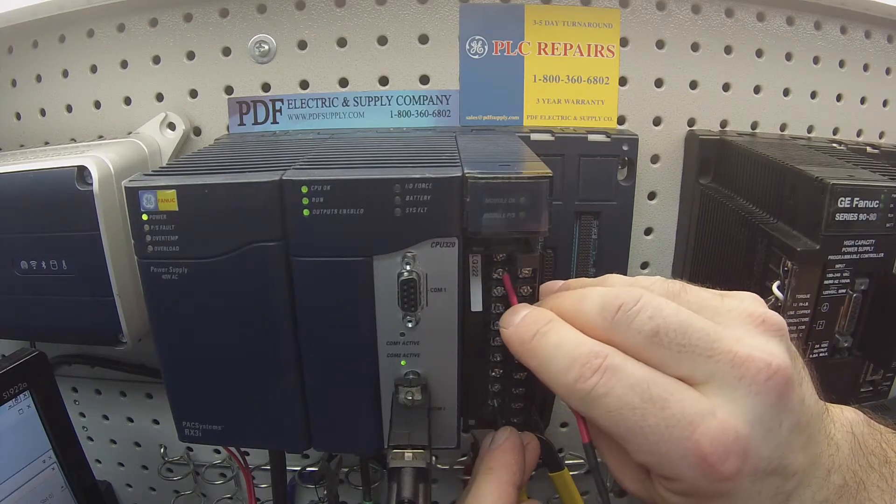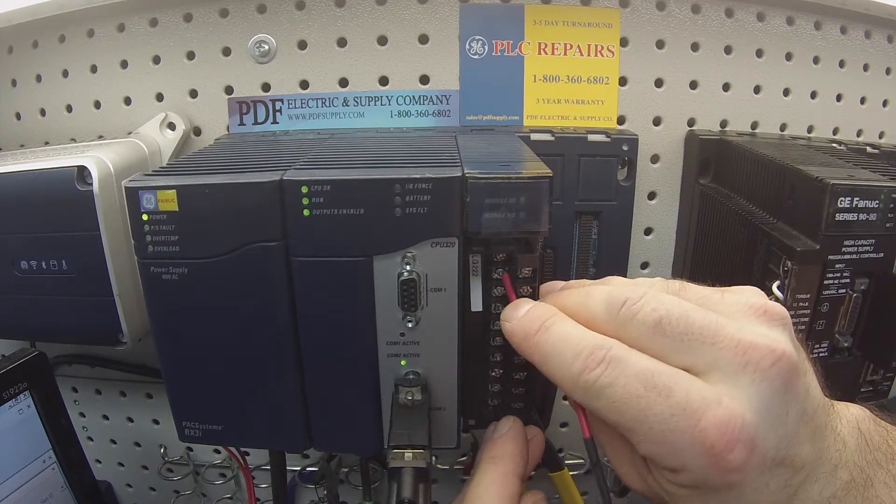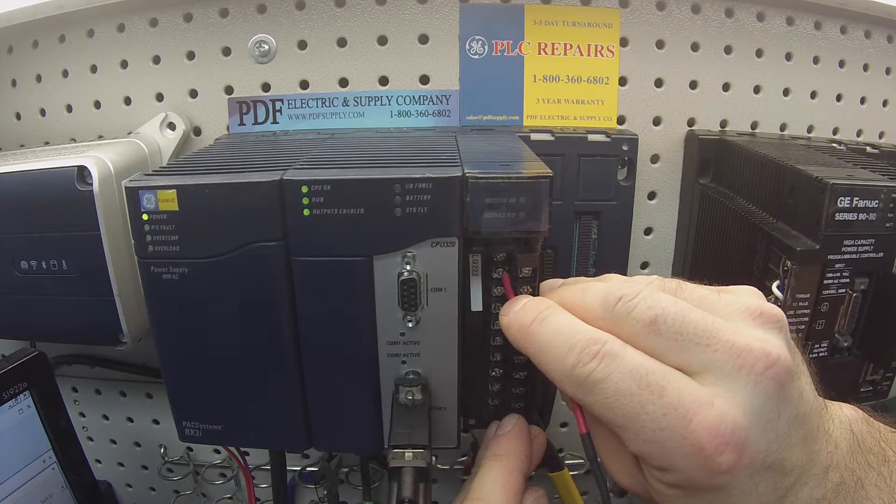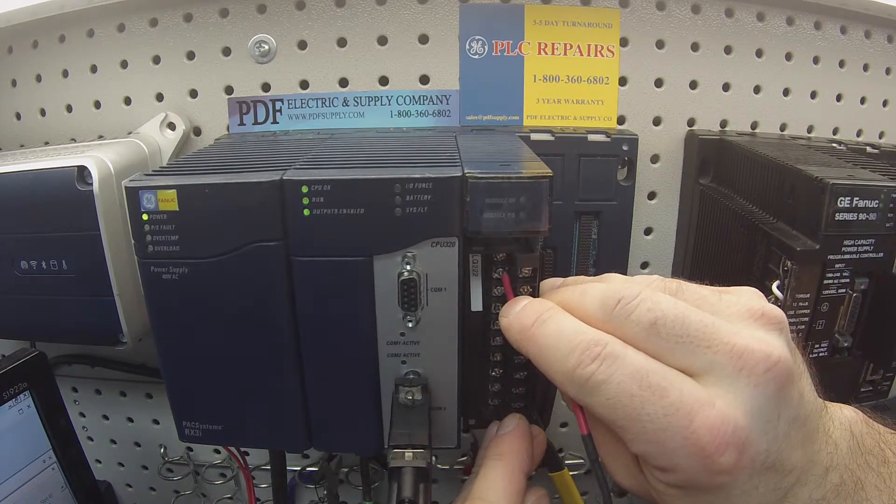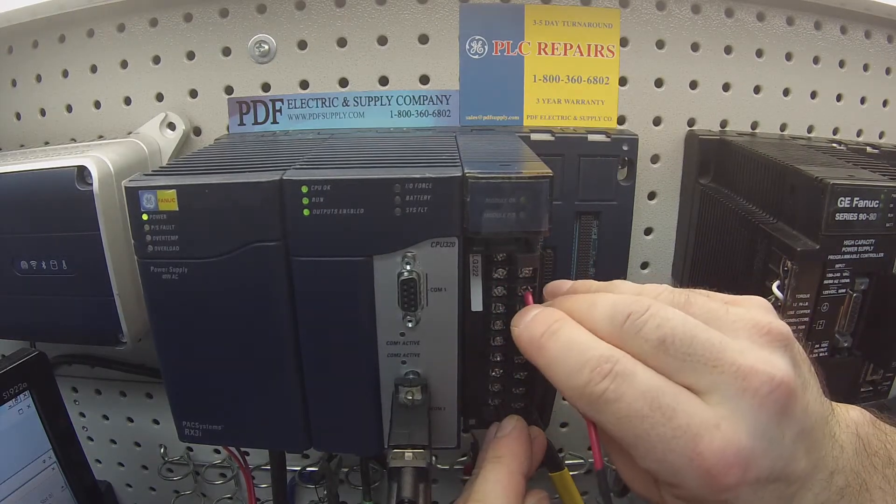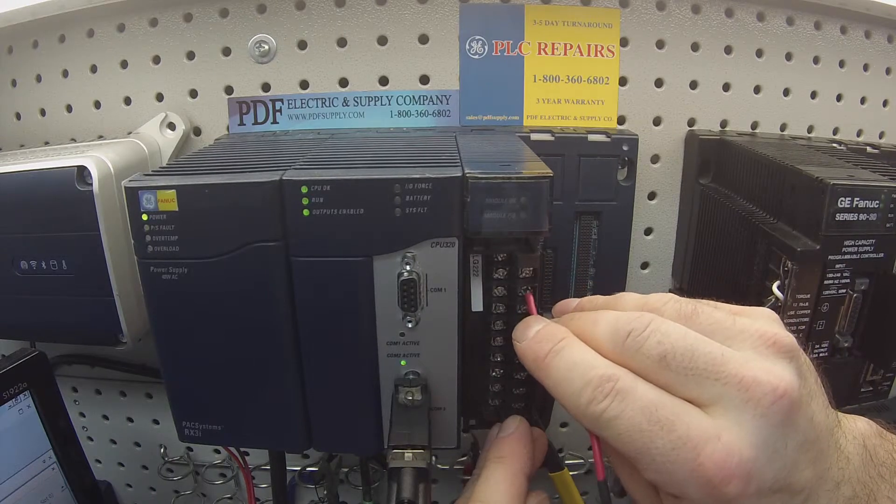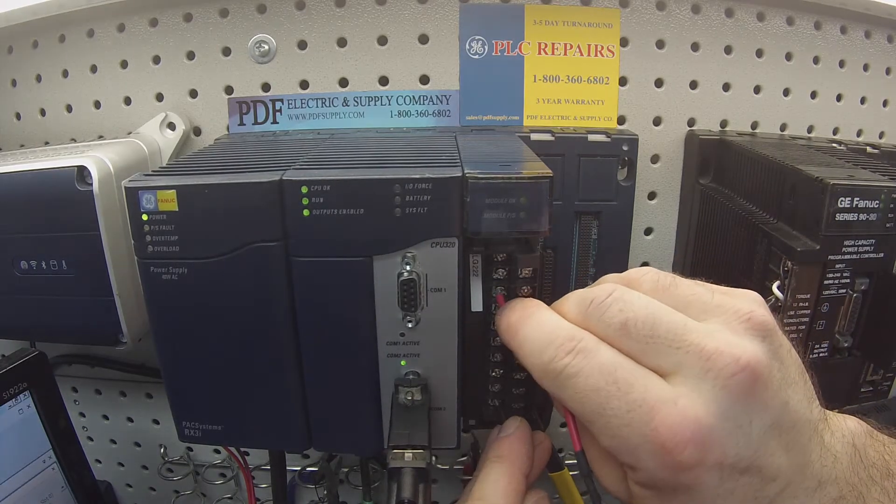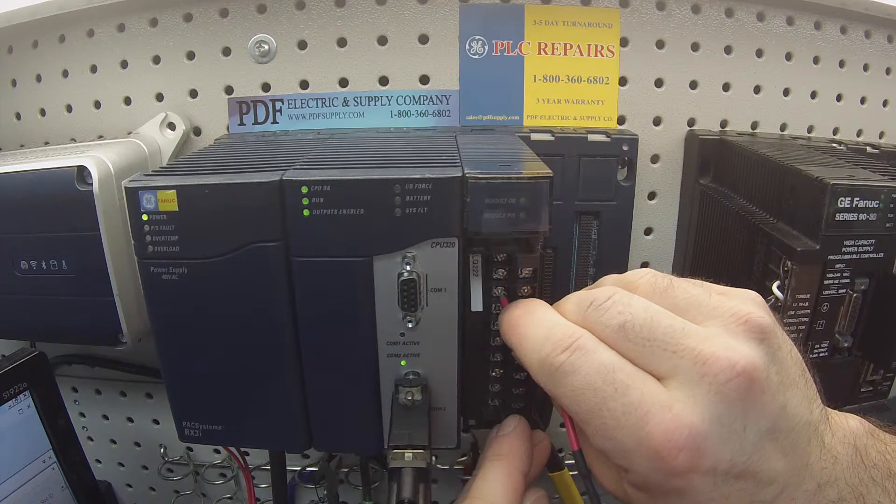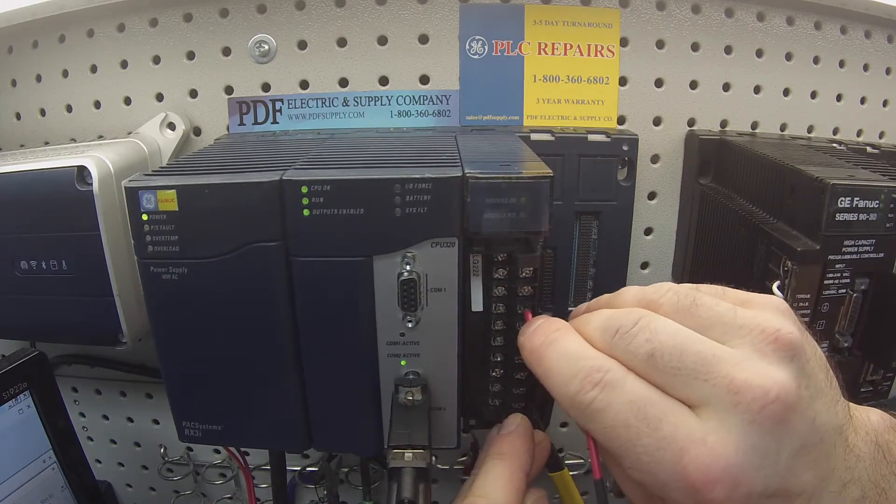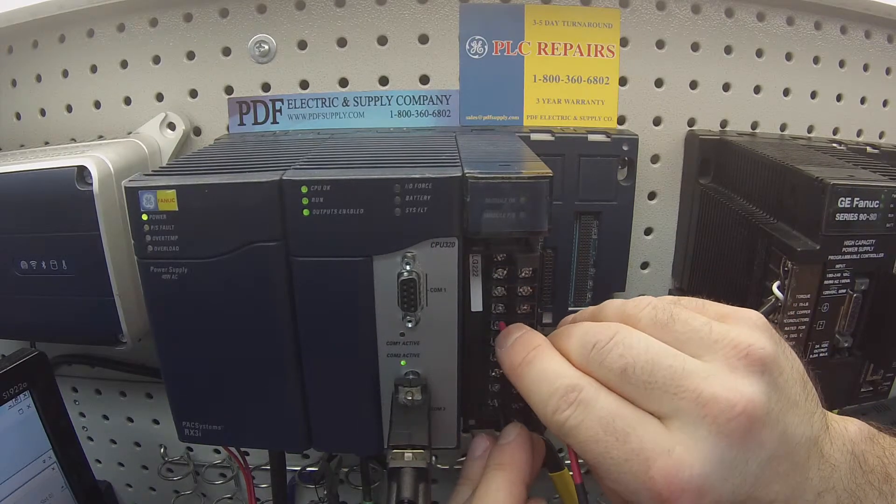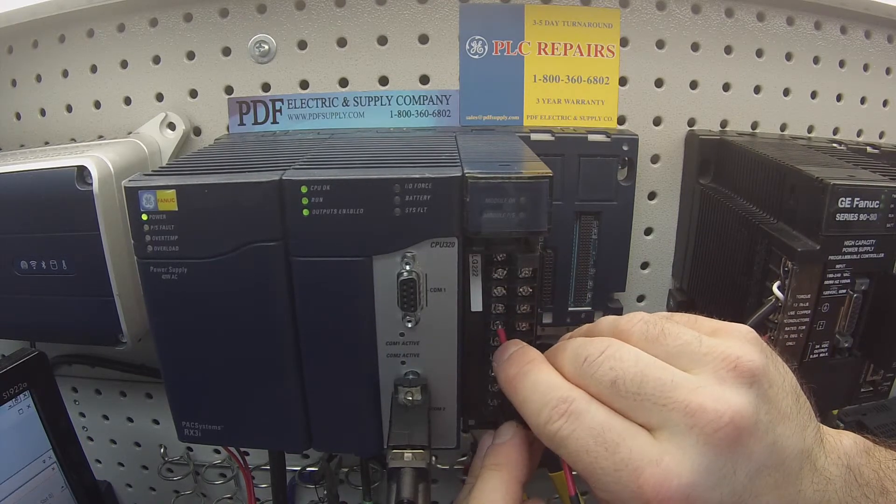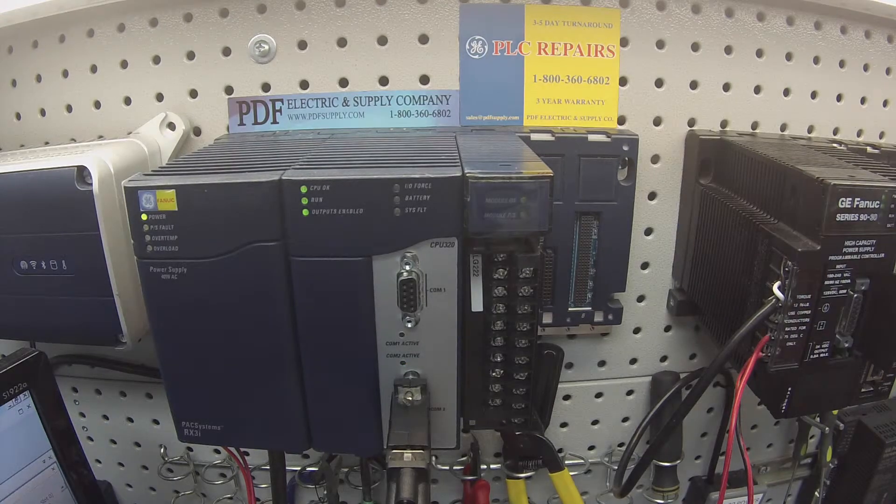Based on a scale value, a maximum scale value of 32,000, three volts should be somewhere in the neighborhood, give or take, of 10,000. So I've got 9,736, but it's a fairly stable, solid range that I'm in, very close. All channels are looking the same. Now you go left and right in a zigzagging pattern. I'm now on terminal number four, which is channel number two. Then I'm going to go back to the left-hand side of the terminal and go back and forth. Pay attention to the wiring diagram. I'm going to go through one by one and test each circuit to make sure they're all working, left and right, all 16.